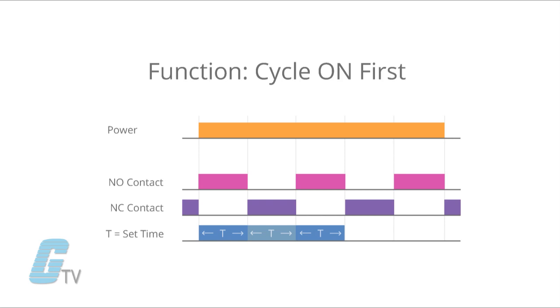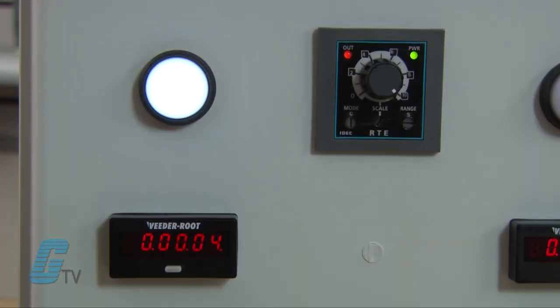In cycle on first timers, the contacts change state when power or a signal is supplied. After a set amount of time, the contacts will change state and timing will begin again. Once the timing has counted up to the set point, the contacts will change state again and turn on. This will continue to cycle on and off until the relay is removed from the power source.